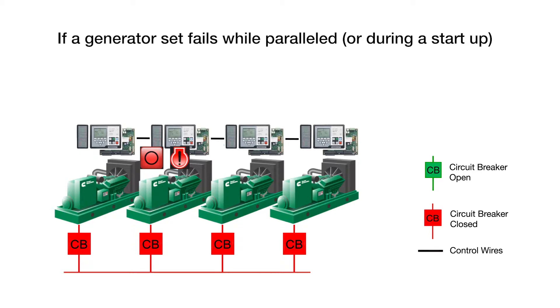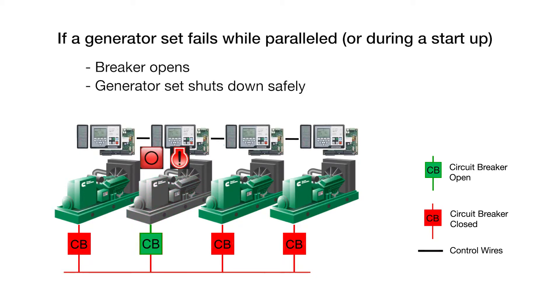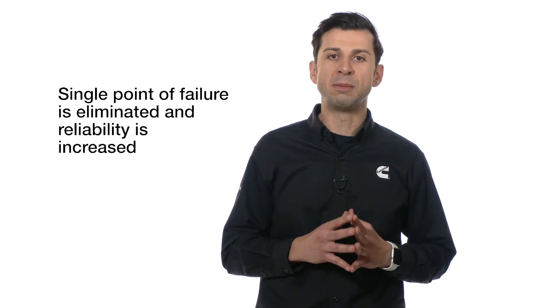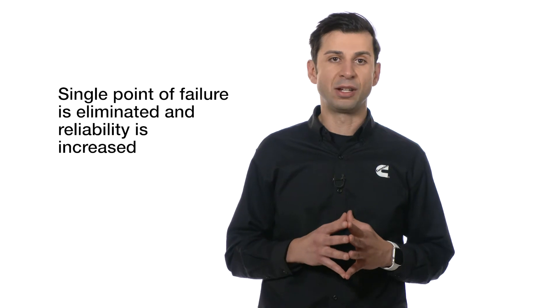If a generator set fails to start or fails while paralleled, the generator set that failed opens its circuit breaker, shuts down safely, and the paralleling operation continues seamlessly without loss of power. Also, by placing the paralleling logic on each generator set and removing it from the master control and/or switchgear, single point failure is eliminated and reliability is increased.